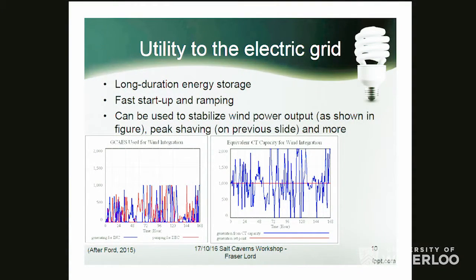CAES and pumped hydro storage are generally the two economically feasible, large-scale, long-duration energy storage facilities. CAES has fast startup times, fast ramping ability — usually 10% to 20% per minute, which is good even by natural gas turbine standards. It can be used for a multitude of purposes, such as integrating wind power into our grid. For example, a study by Andrew Ford for Ontario found that to balance wind farm output to a steady 1,000 megawatts, we would need 1,000 megawatts of CAES production and 1,000 megawatts of compression power, almost totally leveling the output.